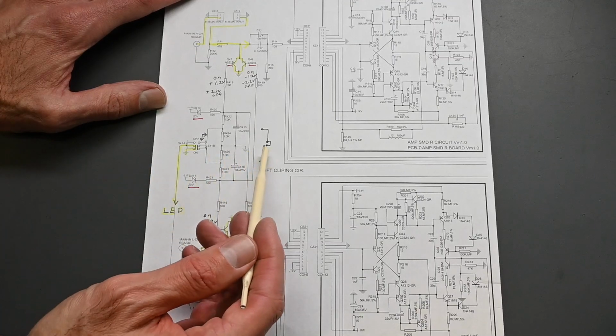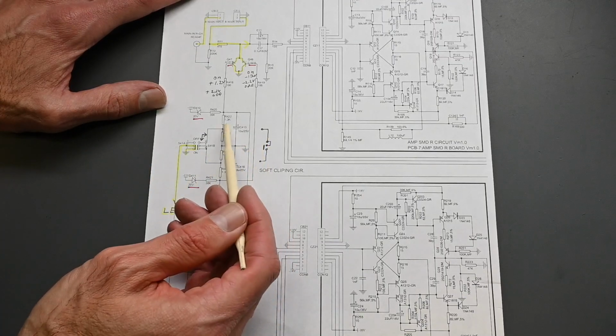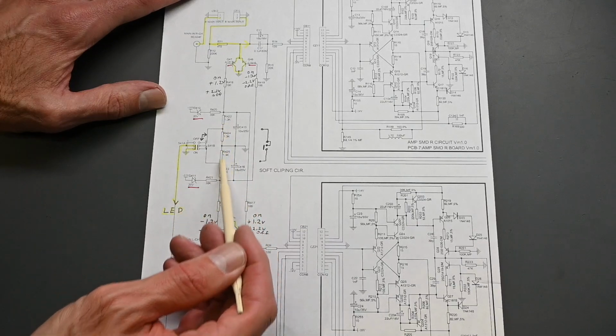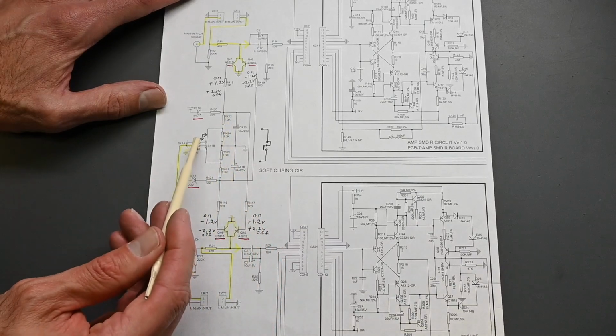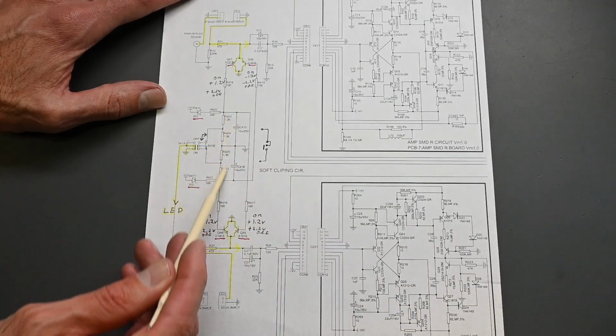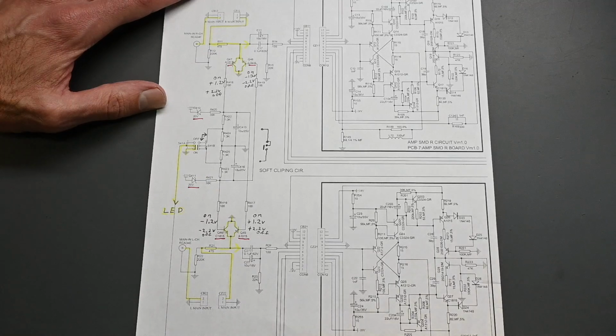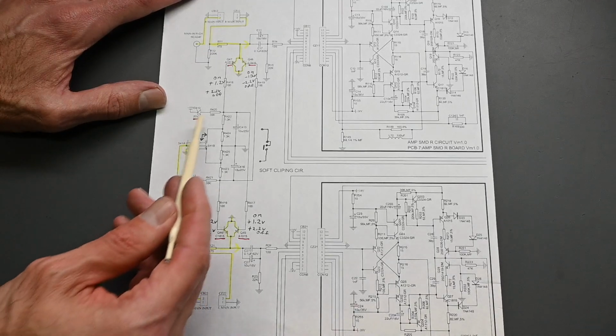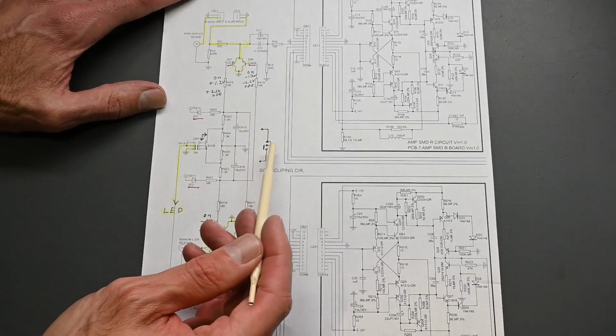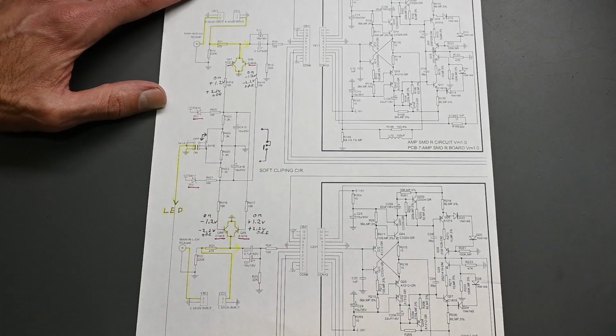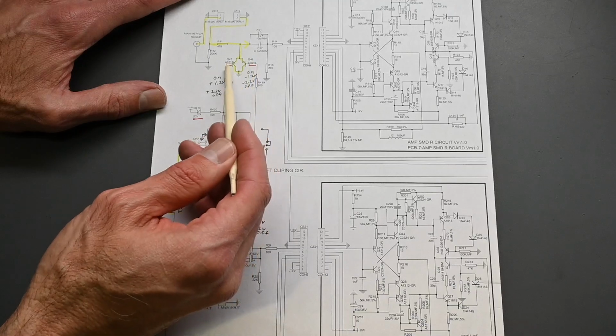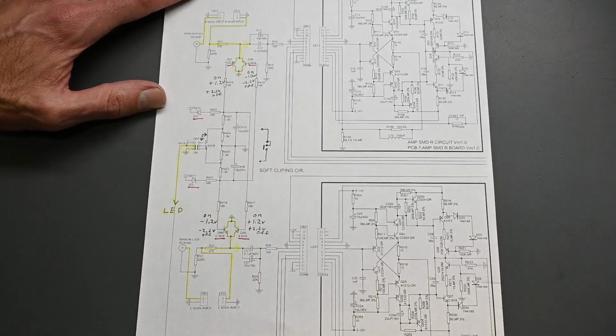Going to the other position, if this is opened up, that's when this part of the circuit has all 4 resistors in series. In the off position, all 4 in series is 5.2k ohms, and we were seeing very close to that value. So if you're troubleshooting this part of the circuit, remember this is how the switch should actually be drawn. These components with little red marks next to them are all the ones that were replaced.